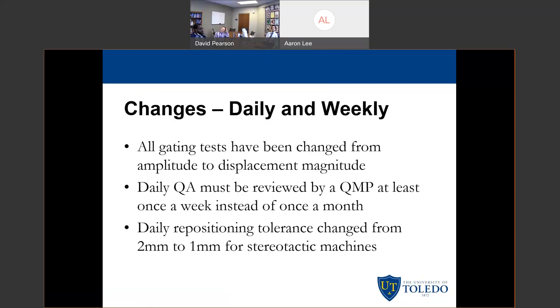This change ensures that the system is able to correctly measure amplitude. With the original phase-based testing approach, you would have no idea if your system was correctly measuring the height of the patient breathing differently each day. They also said that daily QA must be reviewed by a QMP at least once a week instead of once a month.